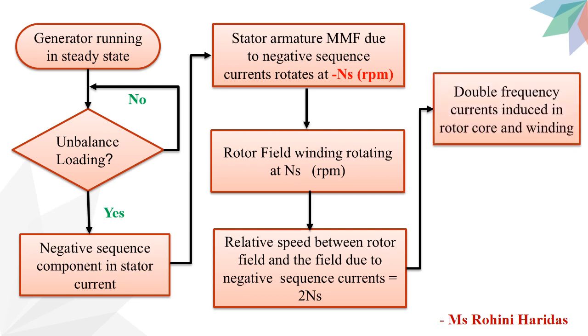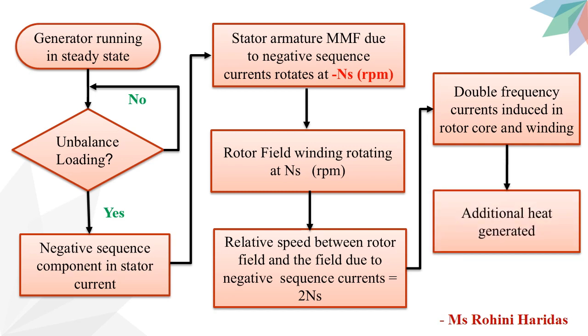This causes a double frequency current of large amplitude to be induced in the rotor. We know that eddy current loss is proportional to the square of frequency and hysteresis loss is proportional to frequency. Both these losses depend upon frequency and will increase due to the double frequency induced current in the rotor, which causes additional heat generation. This will cause severe heating of the rotor and can cause damage to it. Hence, it is necessary to provide protection against unbalanced loading.